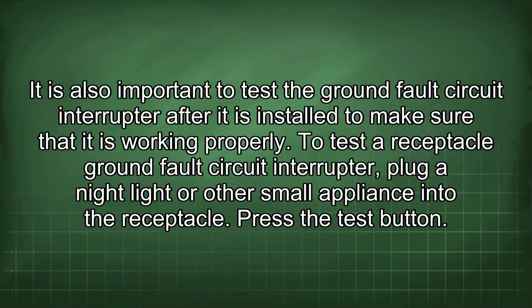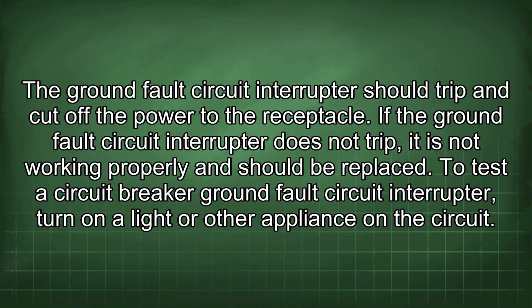To test a receptacle ground fault circuit interrupter, plug a night light or other small appliance into the receptacle. Press the test button. The ground fault circuit interrupter should trip and cut off the power to the receptacle. If the ground fault circuit interrupter does not trip, it is not working properly and should be replaced.